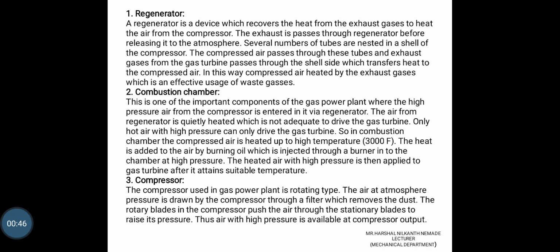Regenerator. A regenerator is a device which recovers the heat from the exhaust gas to the air from the compressor. The exhaust is passed through the regenerator before releasing to the atmosphere. Several tubes are nested in the shell of the regenerator. The compressor air passes through these tubes and exhaust gases from the gas turbine pass through the shell side, which transfer the heat to the compressed air. In this way, compressed air is heated by the exhaust gas, which effectively uses the waste gases.